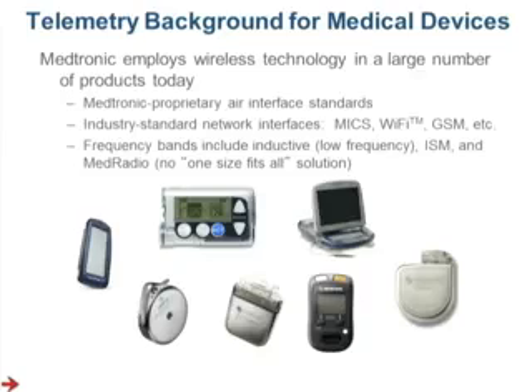Generally these are inductive in nature, historically. With the data rates we had and the need for clinical follow-up, a proximal inductive telemetry system was acceptable. Especially when you look at some of the original generation devices - you'd get a screwdriver, and your nurse would have a screwdriver with a sharp edge, and they would actually stick it through your skin and turn a trim pot to adjust your pacing rate. So everyone wanted to quickly move to telemetry, and we had the inductive systems.